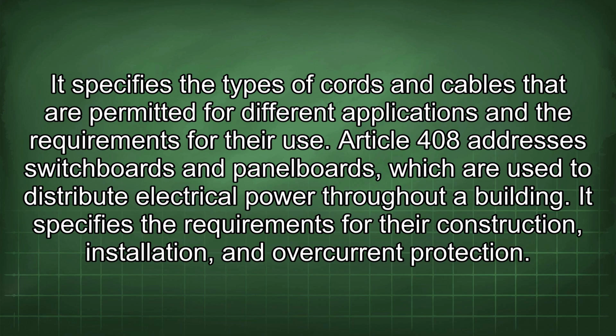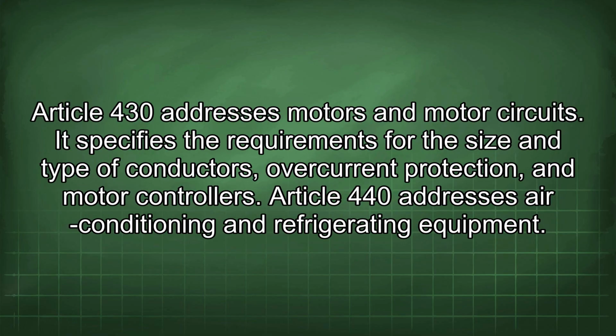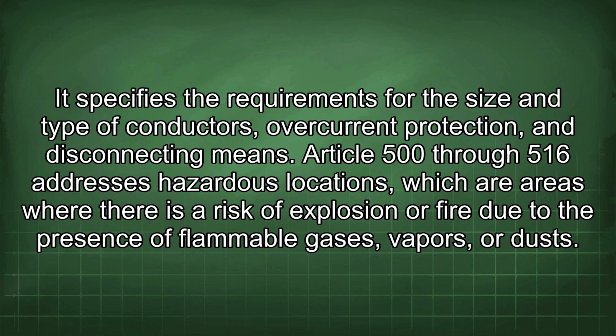Article 408 addresses switchboards and panel boards, which are used to distribute electrical power throughout a building. It specifies the requirements for their construction, installation, and overcurrent protection. Article 430 addresses motors and motor circuits. It specifies the requirements for the size and type of conductors, overcurrent protection, and motor controllers. Article 440 addresses air conditioning and refrigerating equipment. It specifies the requirements for the size and type of conductors, overcurrent protection, and disconnecting means.